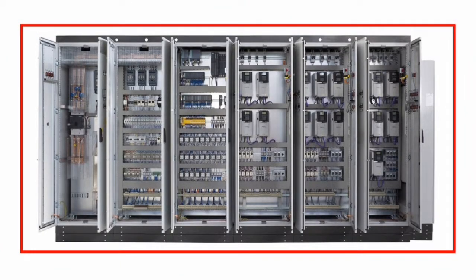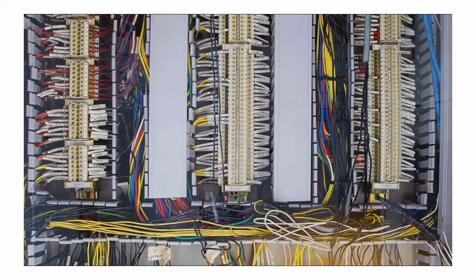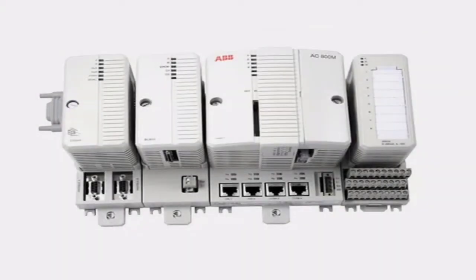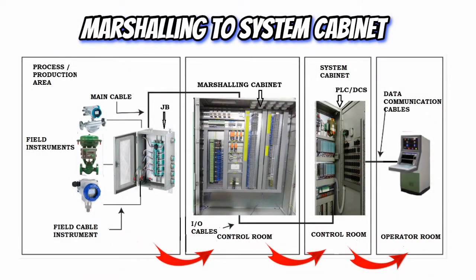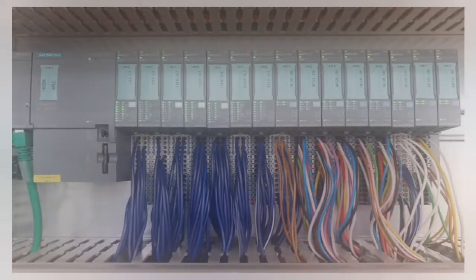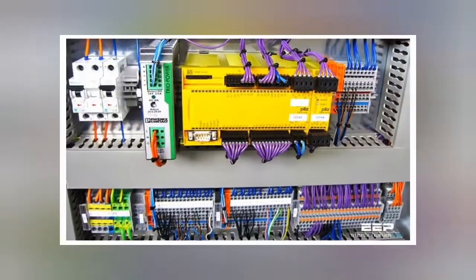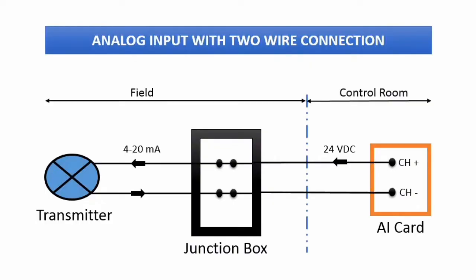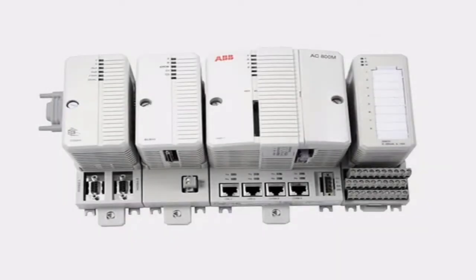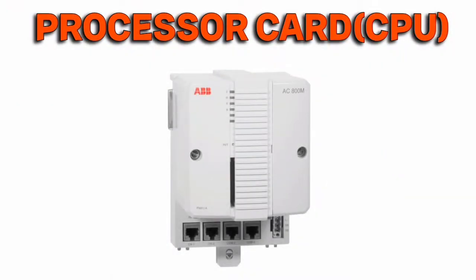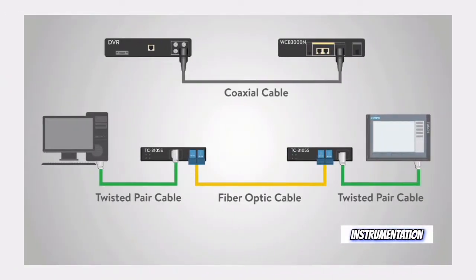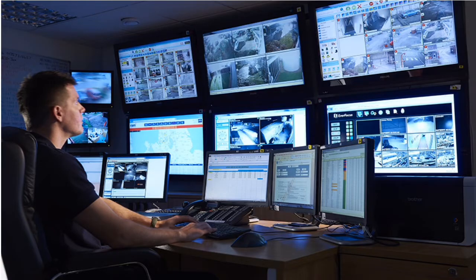Once the main cables are terminated in the marshaling cabinet, we have to route these field devices to their respective analog input card channels. We use internal wiring to route the field devices from the marshaling cabinet to the system cabinet. The analog input card converts the 4 to 20 milliamp signal coming from the field devices into an equivalent digital signal in binary codes, which is then communicated to the processor card. The processor card performs as per predefined or programmed instructions, and may have an inbuilt or separate Ethernet communication link used to display the measured process variables on the workstation.